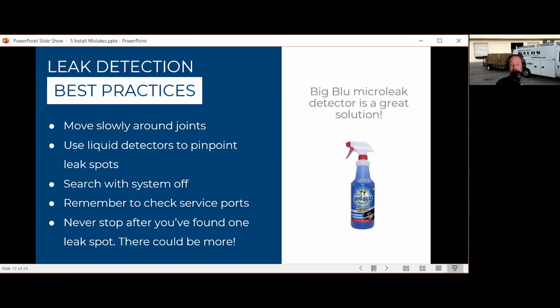Now, even finding bubble leaks, really small ones, is a skill, an acquired skill, because it requires a lot of patience. It's not like every leak makes these gigantic bubbles. Little tiny micro leaks make little tiny micro bubbles, and you have to get used to spotting those. There's lots of videos online. Bert's very proud of how good he is at finding those, and it is a talent of itself. But always be looking for oil, always be listening, and use those soap bubbles to find them.